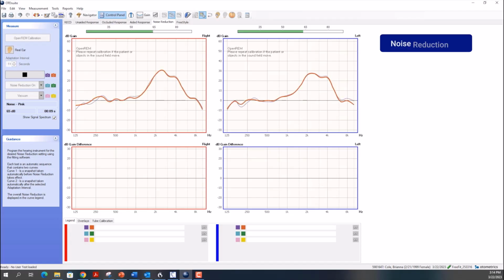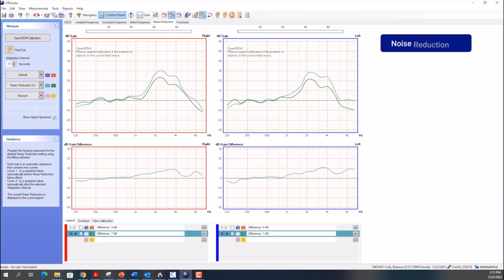Finally, we tested the noise reduction capabilities both with noise reduction turned off and again with noise reduction turned on. In the off setting, we measured a 5 dB reduction in steady state noise, and with it turned on, it increased the noise reduction by another 2 dB to reach 7 dB of noise reduction.